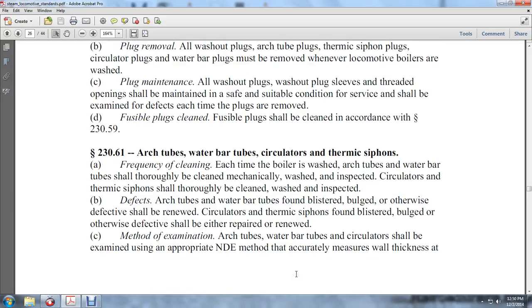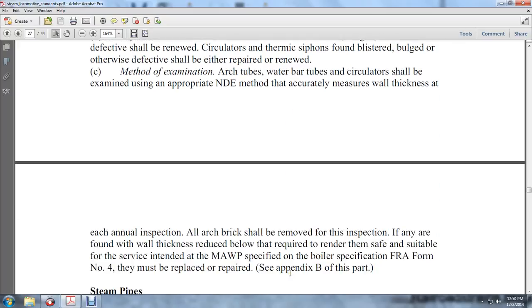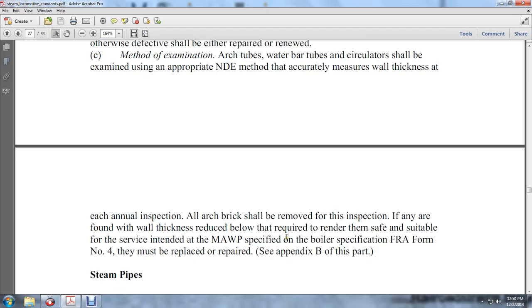Wall thickness shall be accurately measured at each annual inspection. All arch brick shall be removed for this inspection. If a component is found with wall thickness reduced below that required to render it safe and suitable for the service intended with the MAWP specified in the boiler specification of FRA Form No. 4, it must be replaced or repaired per Appendix B of this part.